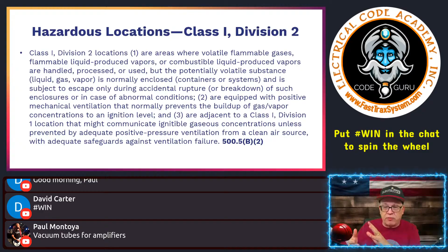So handling any of those volatile fuels, processing, exchanging, things like that, that could cause a problem. Okay, then that is a Class 1 Division 2 location. So it says handling, processing, or used, but the potentially volatile substance, liquid, gas, or vapor, is normally in enclosed containers or systems. Okay, so like storage. And is subject to escape only during accidental rupture or breakdown of such enclosures, or in cases of abnormal condition.